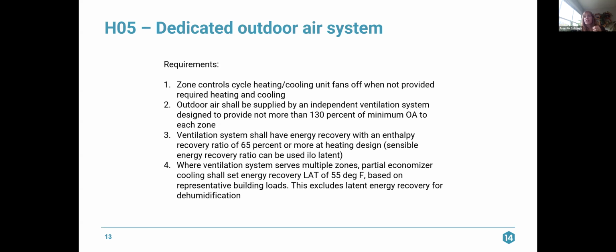Where the ventilation system serves multiple zones, partial economizer cooling shall set the energy recovery leaving air temperature at 55 degrees based on representative building loads. This excludes latent energy recovery for dehumidification. So the idea here is that if it is cool enough and the building is in cooling, we want to provide outdoor air economizer temperature air to the building rather than using our energy recovery. So we're going to bypass that energy recovery wheel when it makes sense.